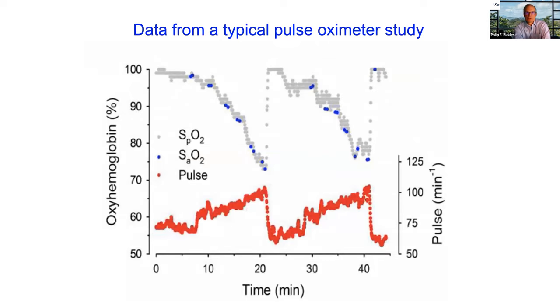Data from a typical pulse oximetry study would look like this. These blue dots are when the blood draws are made. The gray lines are the saturation levels measured with a reference pulse oximeter device. You can see the saturation decreasing or stepping down at different points during the test.